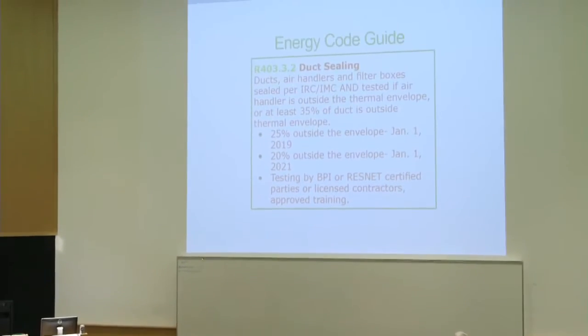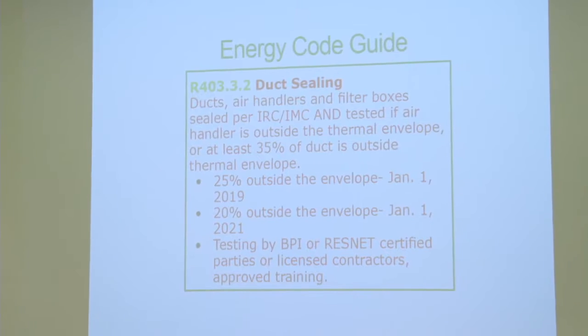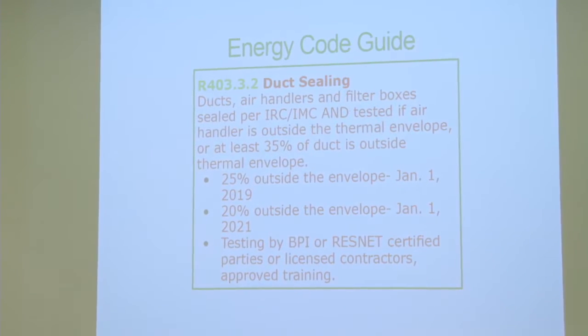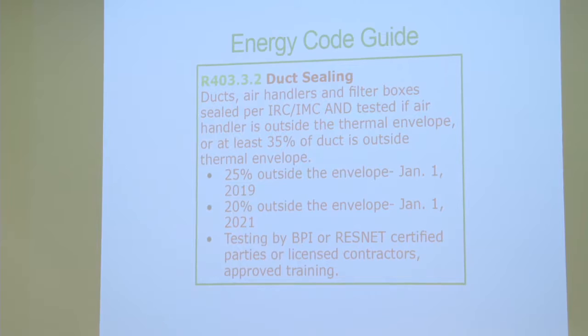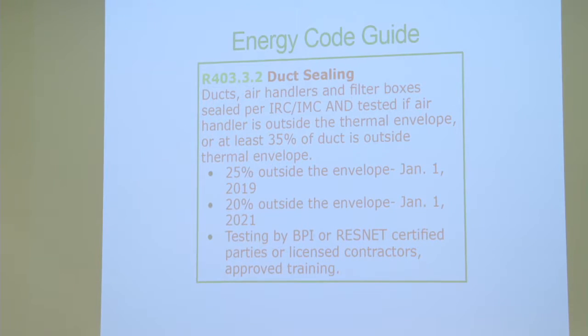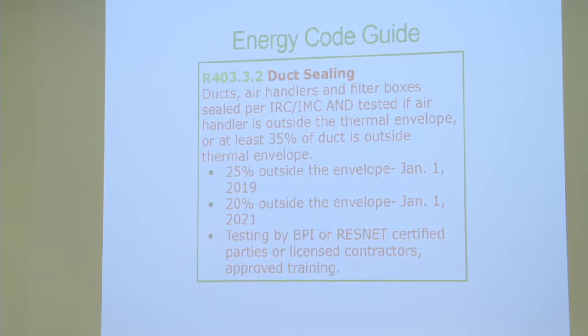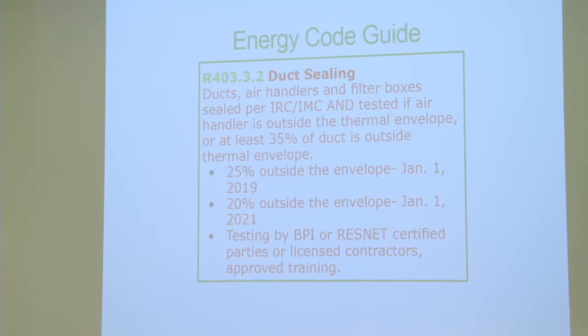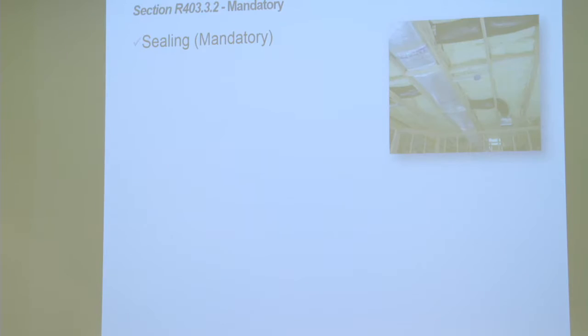Duct sealing. And duct testing. So we got to seal all the ducts, and we have to test it if 35% of the duct is outside the thermal envelope. Some people are still enforcing 50%. The code says if you have duct outside the thermal envelope, you have to pressure test it. The amendment says it's 35%. Next January it goes to 25%, and then January 21 it goes to 20%. The duct needs to be tested.